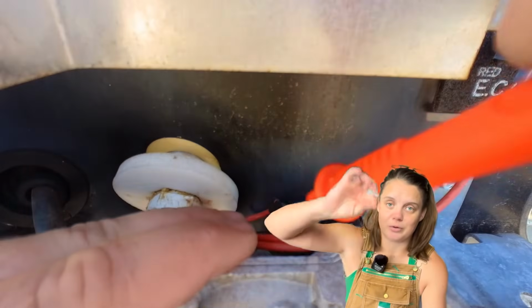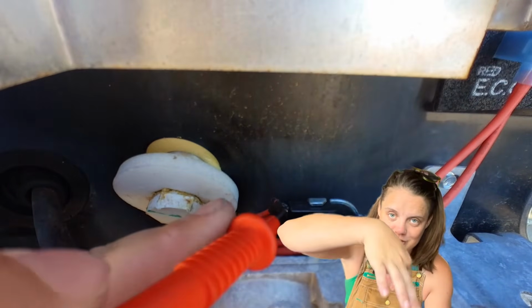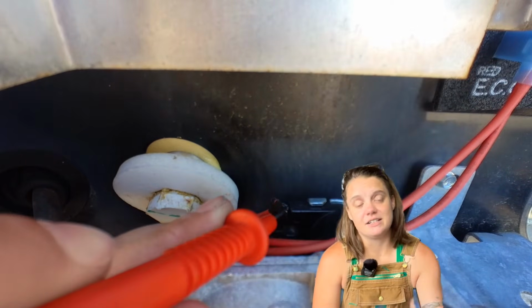There is a way to test if your gas valves are good, but it's a bit more involved than I want to get into on this video. Just know, if power's made it all the way through the ECO, you can put a probe here, find a little bit of metal on that terminal, stick it in, and check for 12 volts, just to make sure the wire between the ECO and your solenoid isn't bad. But for the most part, we're going to use our ears and our nose.